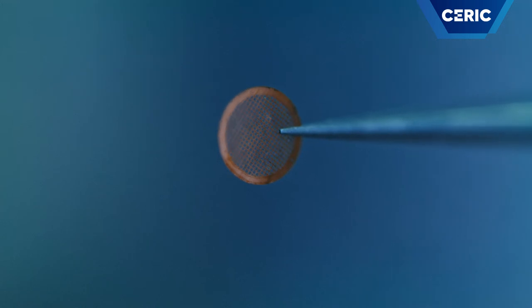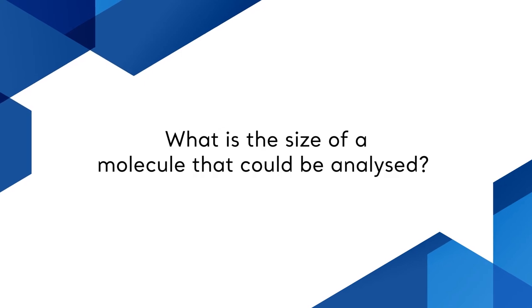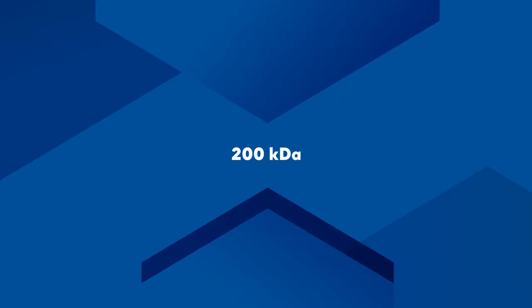The best is to bring frozen and already pre-screened grid. If not possible, then a purified sample in an aqueous buffer should suffice. The applicable range of molecular weight starts from around 200 kD. Even smaller molecules can be studied, but with lower resolution.